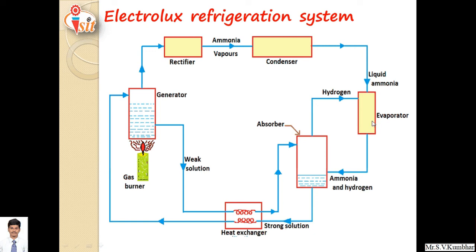In the evaporator, cooling effect is produced. The weak solution formed in the generator is a hot weak solution, which is sprinkled in the absorber. At the same time, low pressure ammonia from the evaporator is passed through this hot weak solution, and strong solution is produced. This strong solution is sent back to the generator. The heat exchanger is used for heat recovery — the hot weak solution exchanges heat with the strong solution, so it takes less time to heat in the generator.